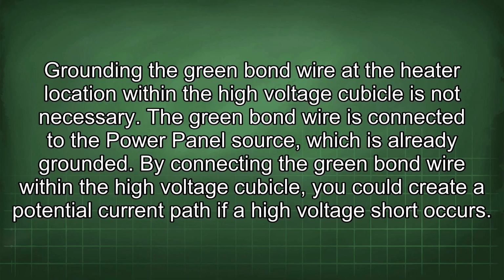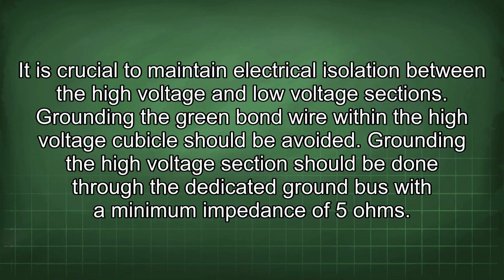Grounding the green bond wire at the heater location within the high voltage cubicle is not necessary. The green bond wire is connected to the power panel source, which is already grounded. By connecting the green bond wire within the high voltage cubicle, you could create a potential current path if a high voltage short occurs. It is crucial to maintain electrical isolation between the high voltage and low voltage sections. Grounding the green bond wire within the high voltage cubicle should be avoided.